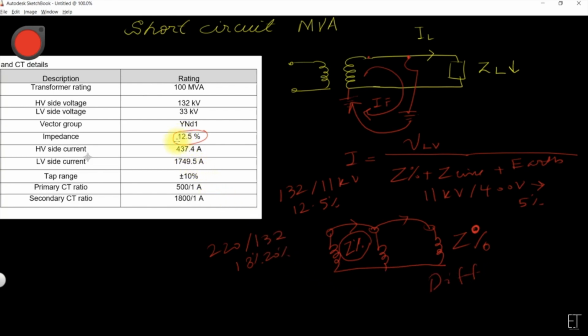Here the percentage impedance is 12.5. If you want to calculate the fault MVA, we already know the formula S equals √3 V into I. This is the formula for normal calculations for the transformer, to calculate the full load current of the HV side and LV side. But the same formula is also applicable for short circuit calculation, as short circuit MVA is equal to √3 V into I.